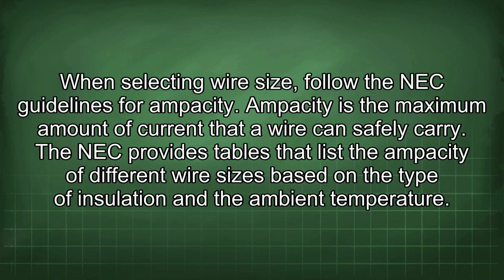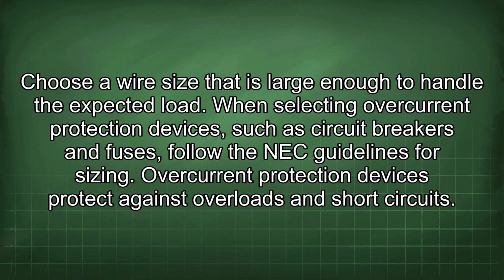When selecting wire size, follow the NEC guidelines for ampacity. Ampacity is the maximum amount of current that a wire can safely carry. The NEC provides tables that list the ampacity of different wire sizes based on the type of insulation and the ambient temperature. Choose a wire size that is large enough to handle the expected load.